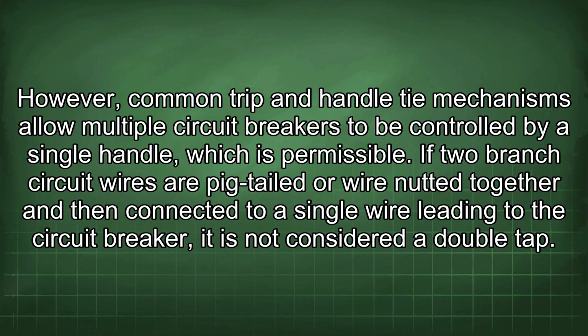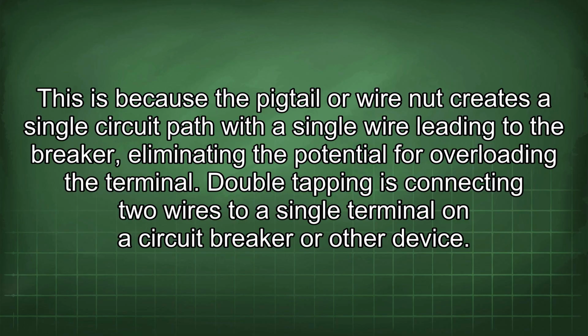However, common trip and handle tie mechanisms allow multiple circuit breakers to be controlled by a single handle, which is permissible. If two branch circuit wires are pigtailed or wire nutted together and then connected to a single wire leading to the circuit breaker, it is not considered a double tap. This is because the pigtail or wire nut creates a single circuit path with a single wire leading to the breaker, eliminating the potential for overloading the terminal.